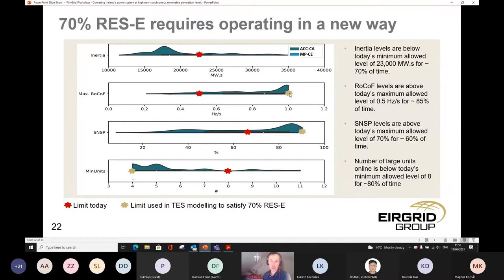we are trialing that at 1 hertz per second. And what the analysis shows is that you absolutely need to operate at this much higher level of RoCoF on the system, because predominantly with a lot of wind and quite a light system, you're going to be experiencing or operating in RoCoFs in that range. So we're kind of at the gold star at the minute, but we absolutely need to be able to stay there into the future.